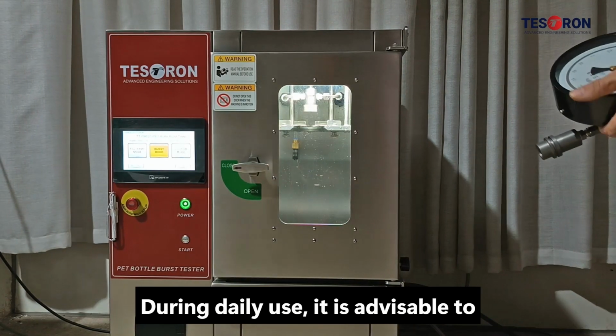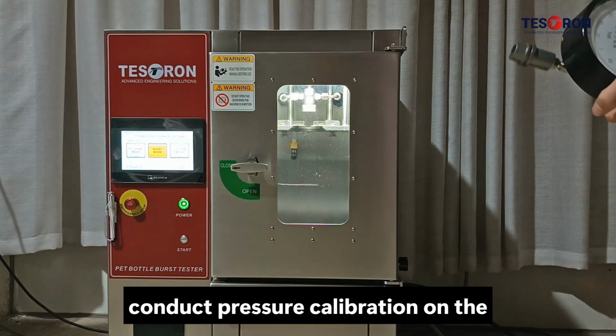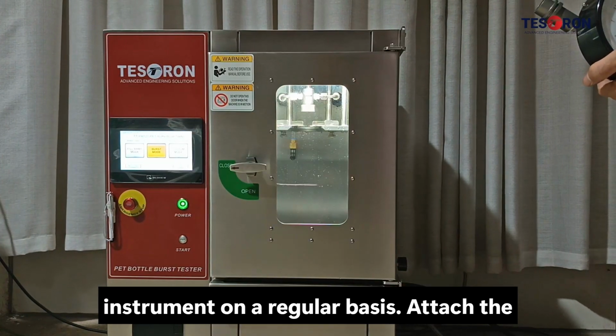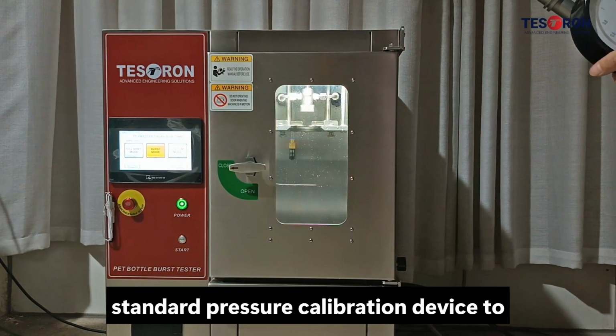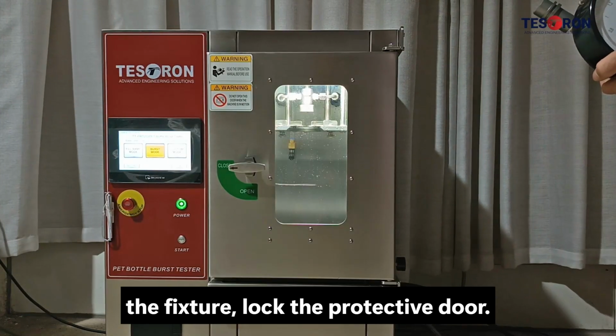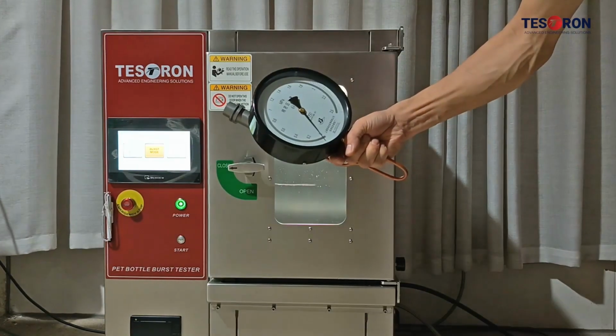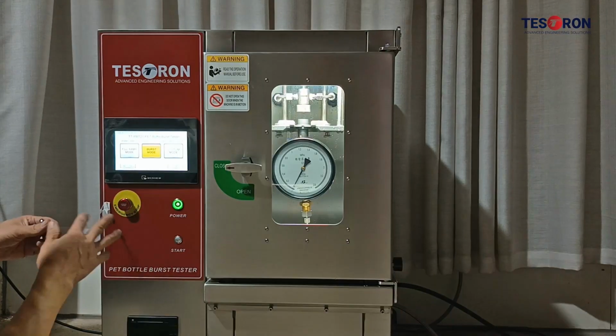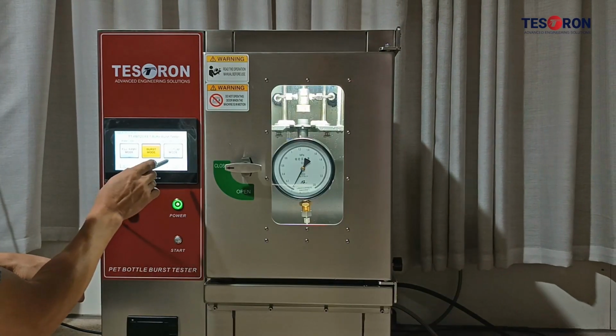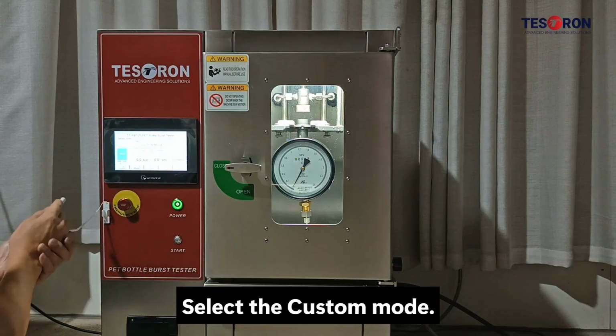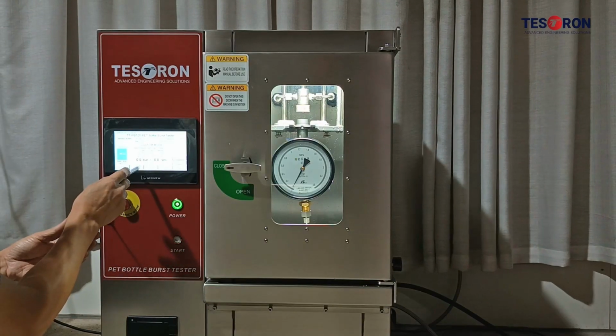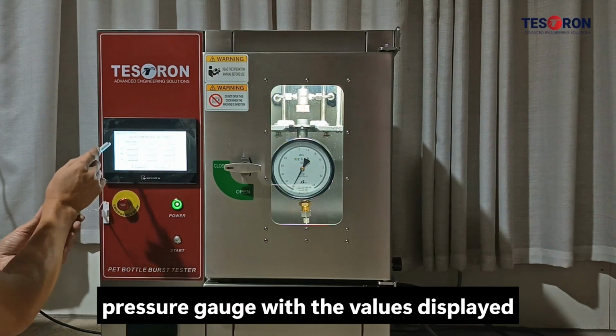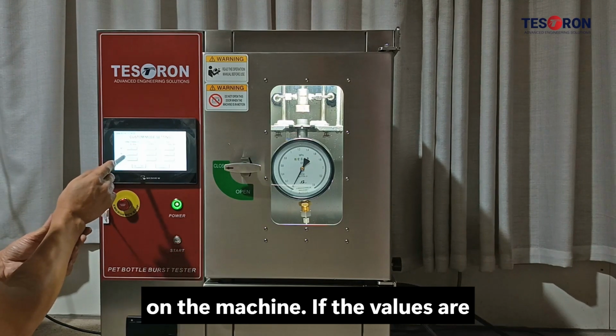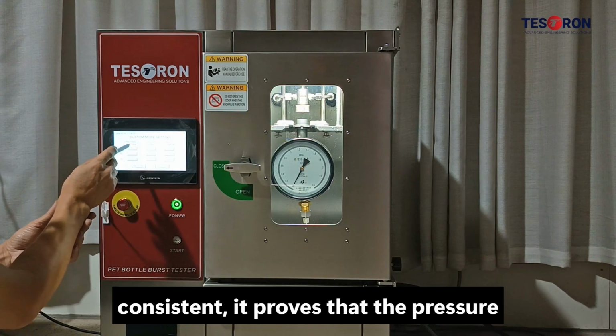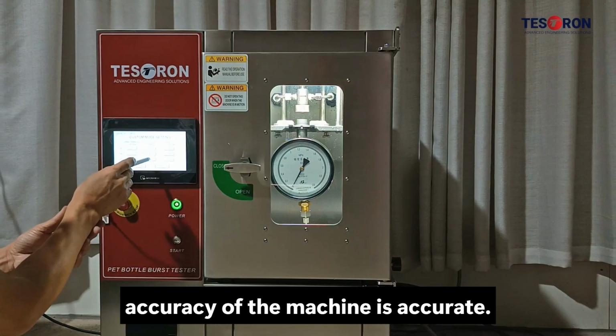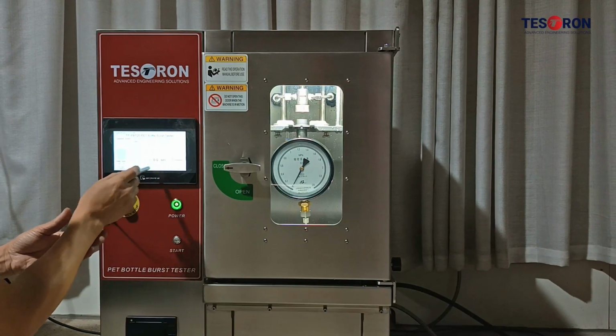During daily use, it is advisable to conduct pressure calibration on the instrument on a regular basis. Attach the standard pressure calibration device to the fixture, lock the protective door. Select the Custom mode. Compare the reading of the precision pressure gauge with the values displayed on the machine. If the values are consistent, it proves that the pressure accuracy of the machine is accurate.